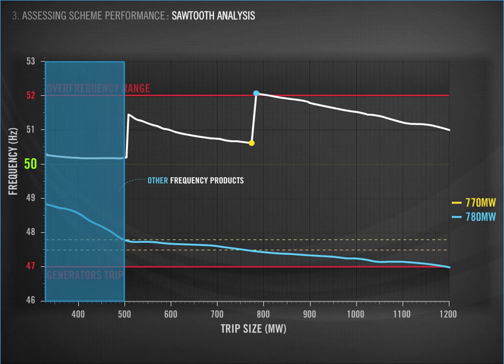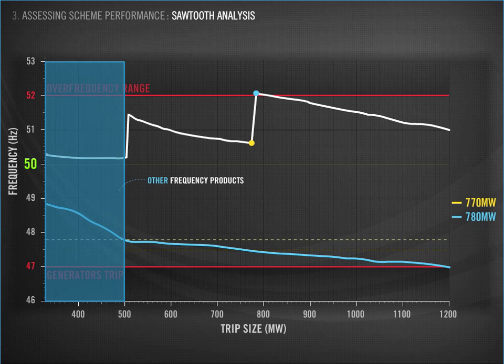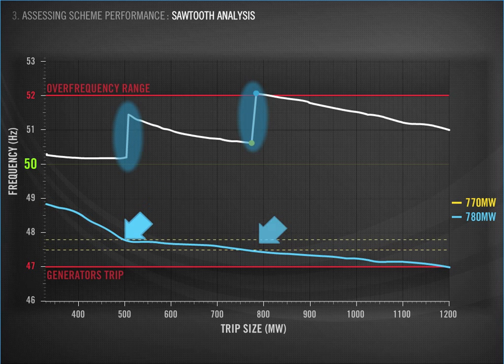The blue block we've highlighted shows event sizes that haven't fallen below the trigger frequency line. They haven't triggered UFLS and are managed using interruptible load and generator reserves. Once the minimum frequency falls below the UFLS settings shown by the blue arrows, then the UFLS blocks will trigger. This results in a tooth that is reflected on the white maximum frequency line. The sharp tooth shows the result of the over-shedding that occurred.